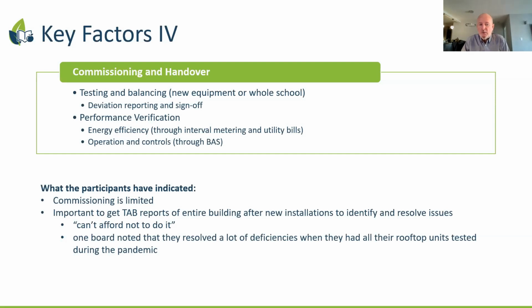What we heard is there's quite limited commissioning that gets done. It's important to test and balance the whole school, not just the new equipment. And this whole area of checking for deficiencies in the system, so that you plug that new rooftop unit into a well-working operation—no fire dampers down, all the equipment working the way it should.